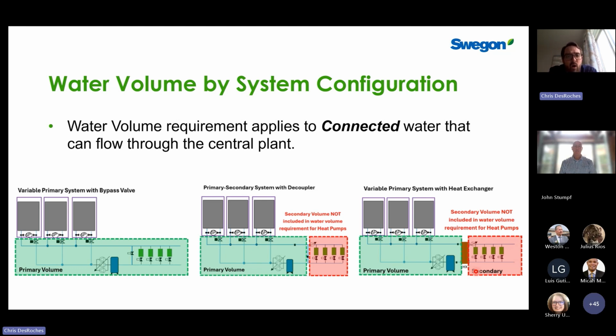Last point I would make on water volume: we tend to use the term water volume or buffer tank kind of interchangeably, but when it comes to these heat pumps, really what it's about is inertia. It's about thermal inertia, having enough connected volume to the heat pumps that can flow through it so that we can buffer what's happening during defrost. So you do get a credit for water content within the pipework, depending on the type of system that you're using. If you're using a full variable primary system where the heat pump units see the water volume through the whole system, you get a credit for the water volume contained in the piping, and generally that will be significant so we can reduce the size of the buffer tank.